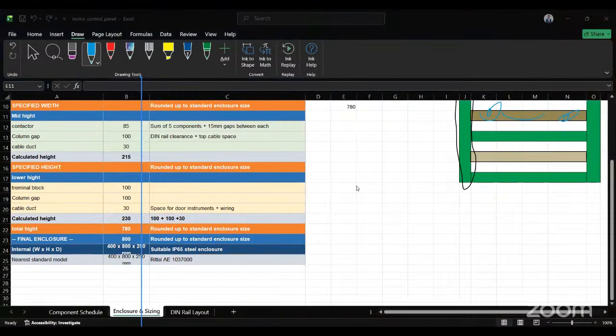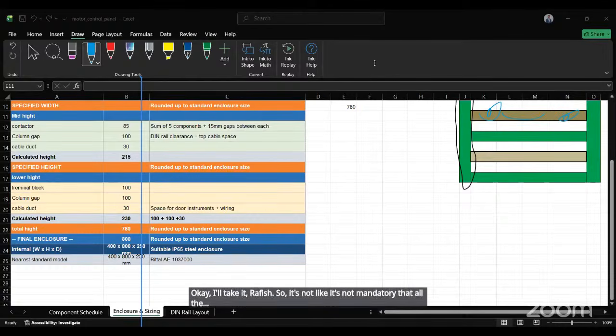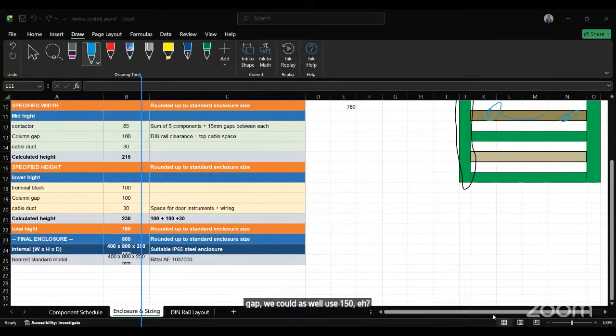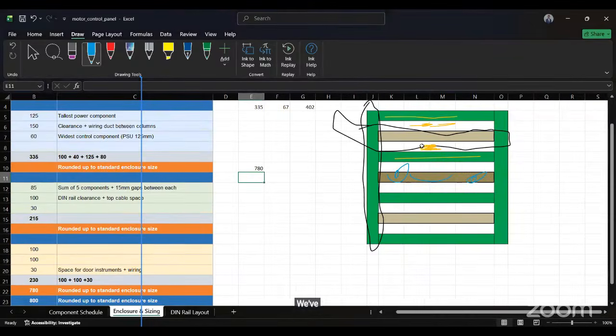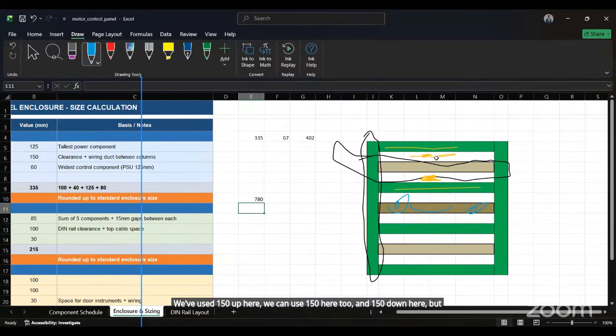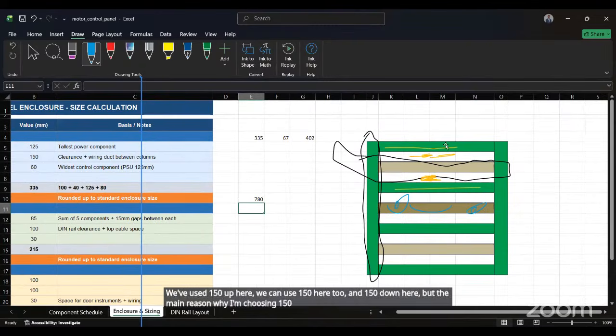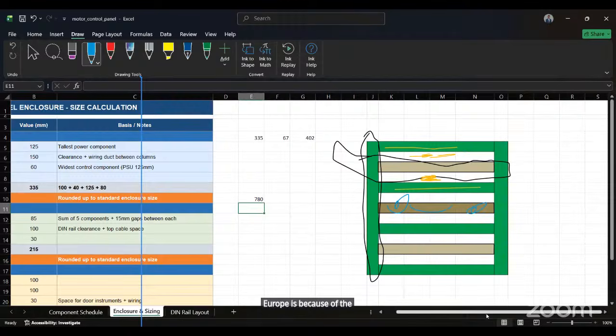That all the columns should have equal gap - it's not mandatory that all the columns should have equal gap. Hope this file will be sent to us, I'll think about it. So it's not mandatory, we could as well use 150 here. We've used 150 up here. We can use 150 here too, and 150 down here. But the main reason why I'm choosing 150 here up is because of the isolator, where the power supply unit we have there.